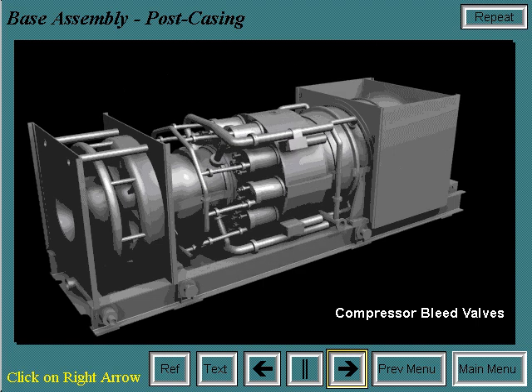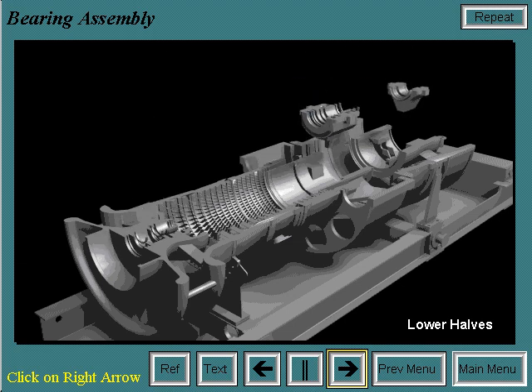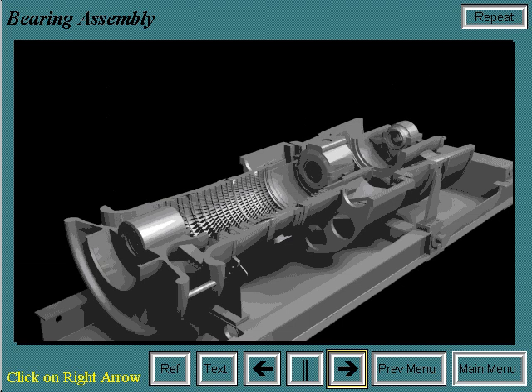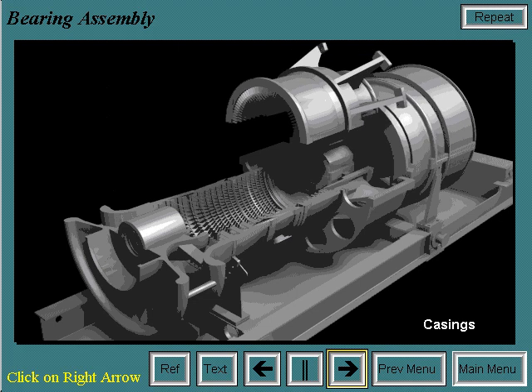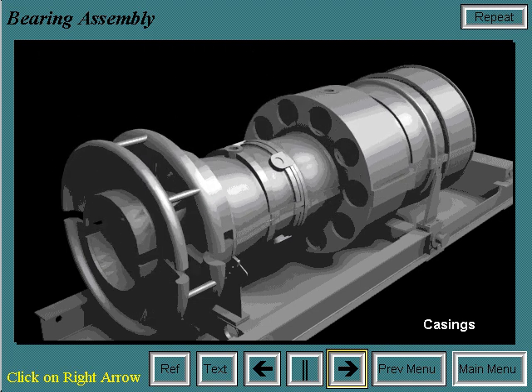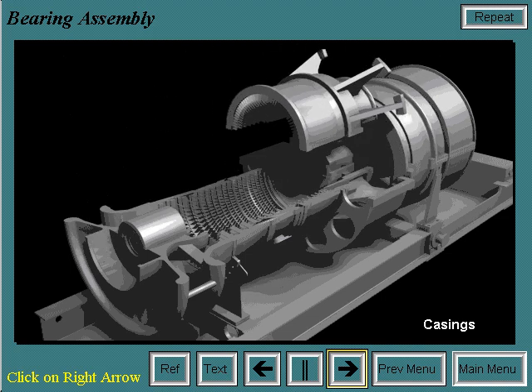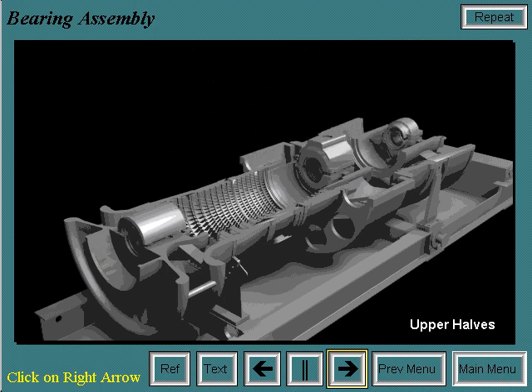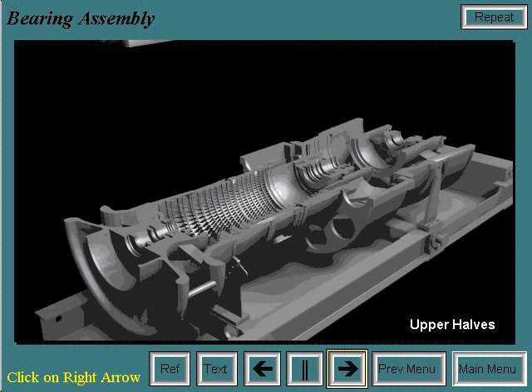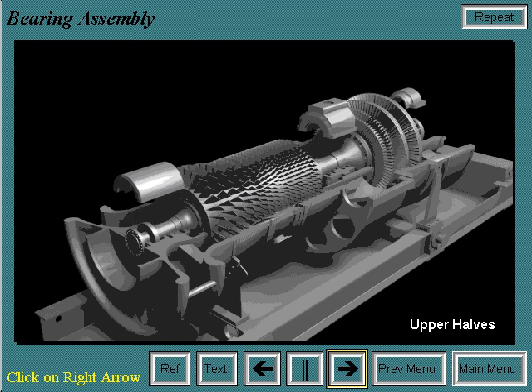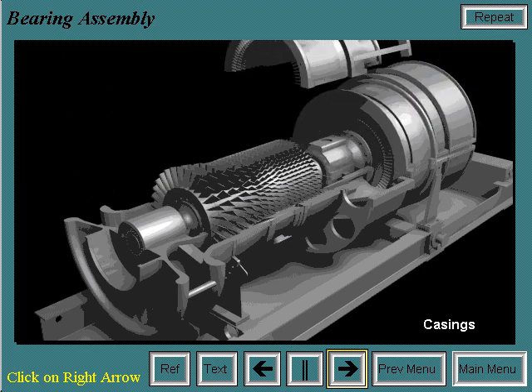The compressor bleed valves are operational during startup and shutdown to protect the unit from surge. The number one bearing is installed in the inlet casing, and the number two and number three bearings and housings are placed into their respective casings. The lower half is put in first, then the upper half of the bearings and housings are installed and aligned with the casings. The upper halves of the bearing housings and casings are then removed and the air seals and oil deflectors are installed. The final step is the installation of the rotor and the upper halves of the bearing housings and casings.